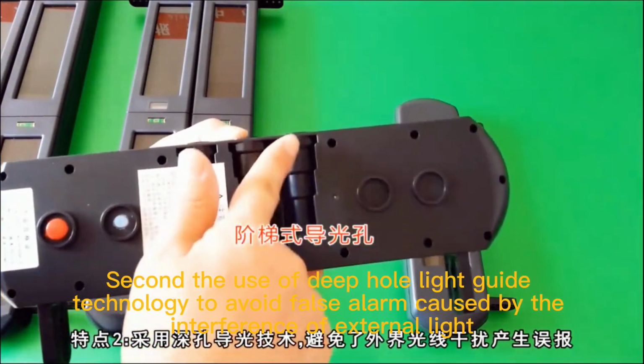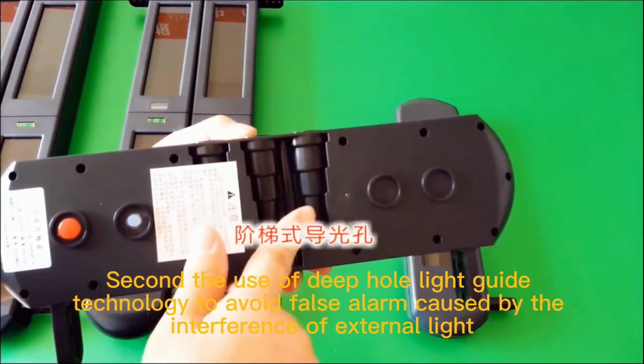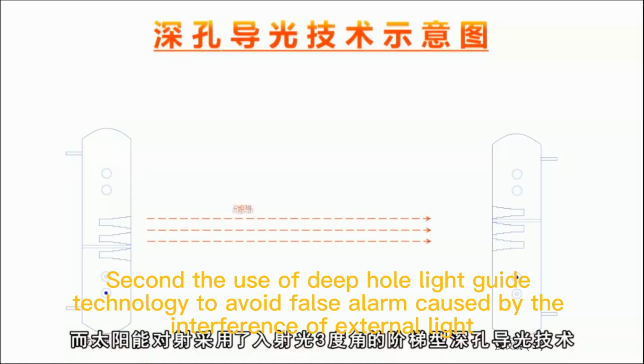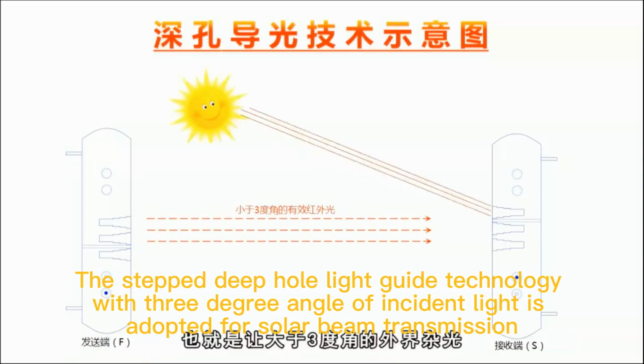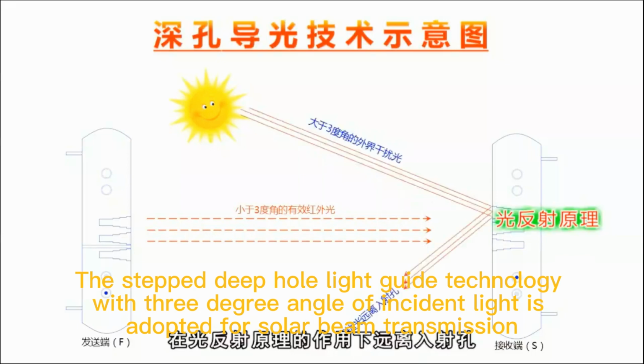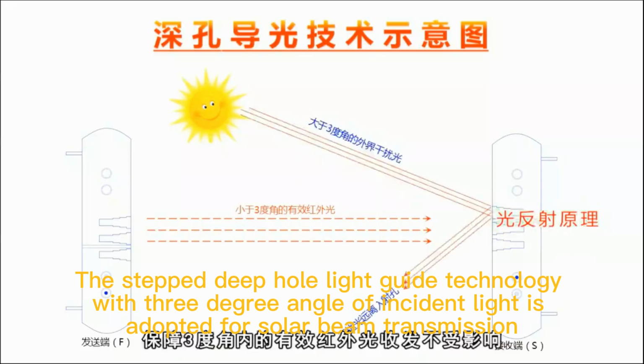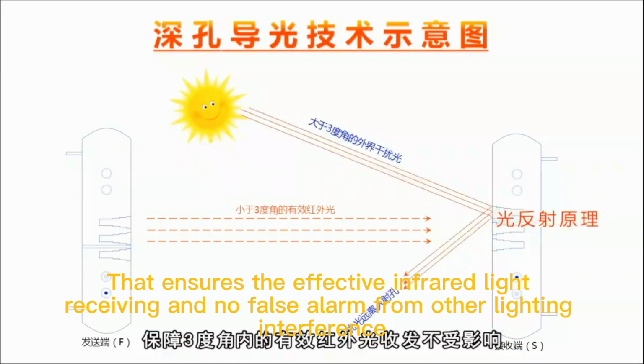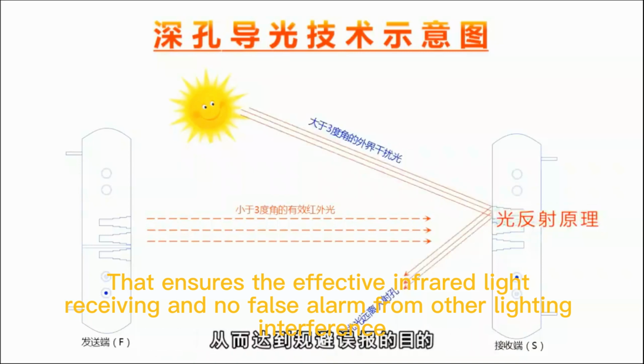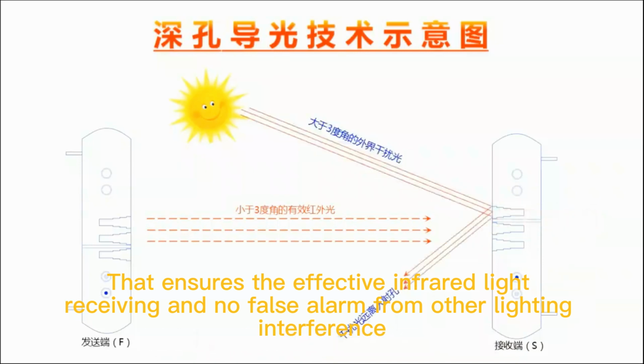Second, the use of deep hole light guide technology to avoid false alarms caused by the interference of external light. The stepped deep hole light guide technology with a 3-degree angle of incident light is adopted for solar beam transmission. That ensures effective infrared light receiving and no false alarm from other lighting interference.